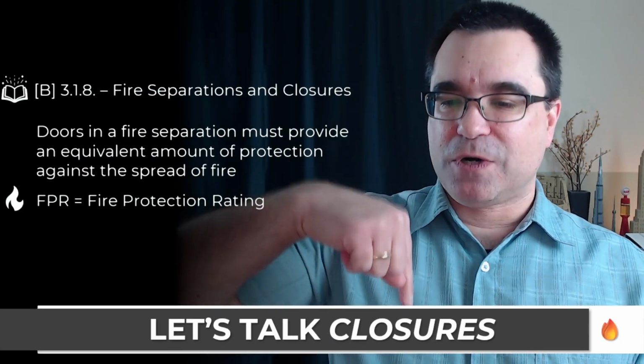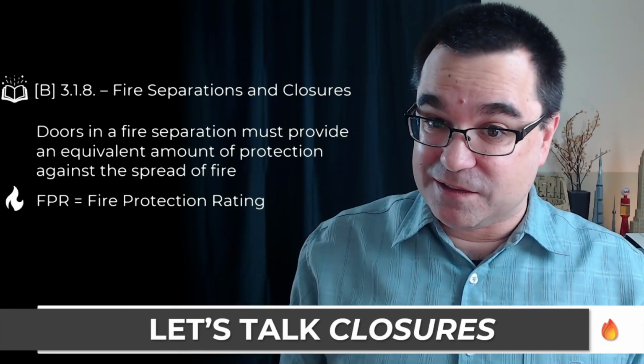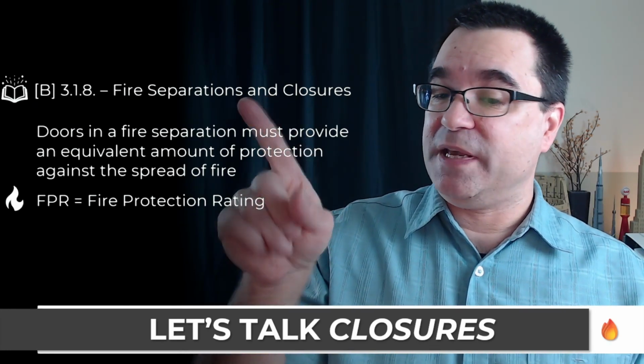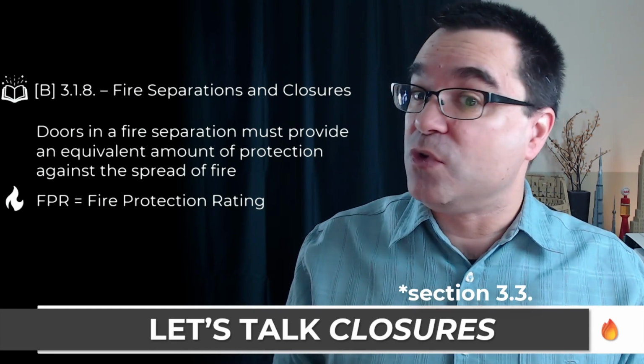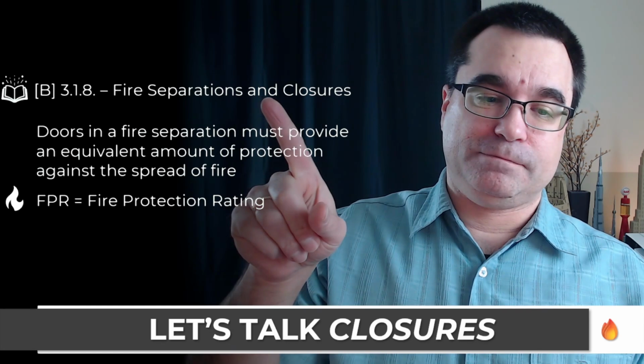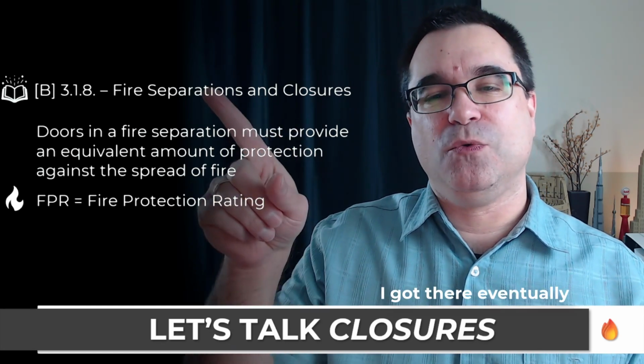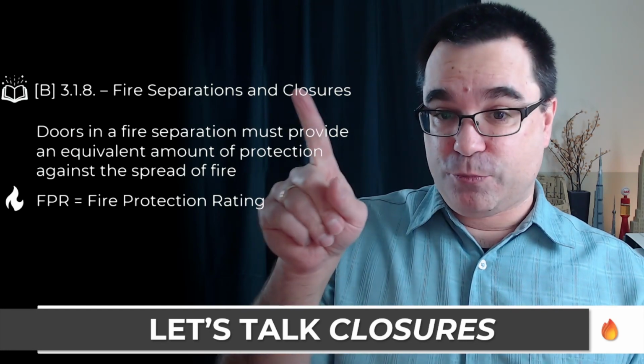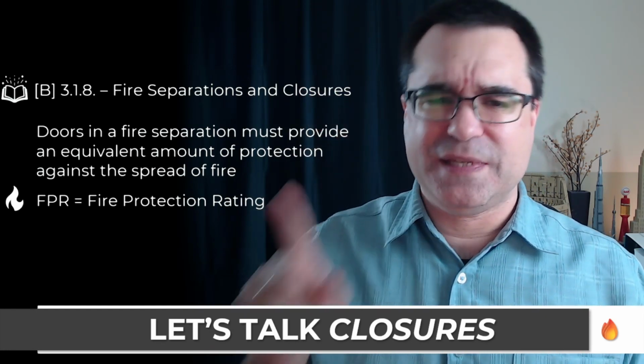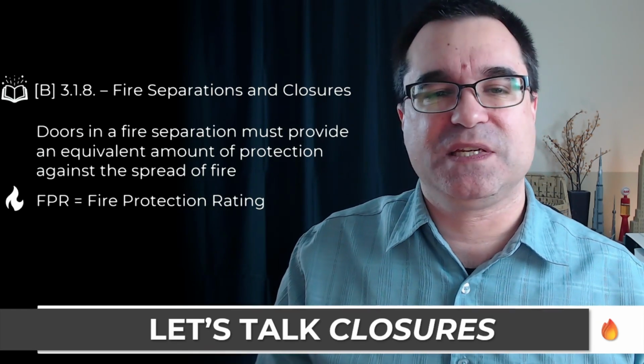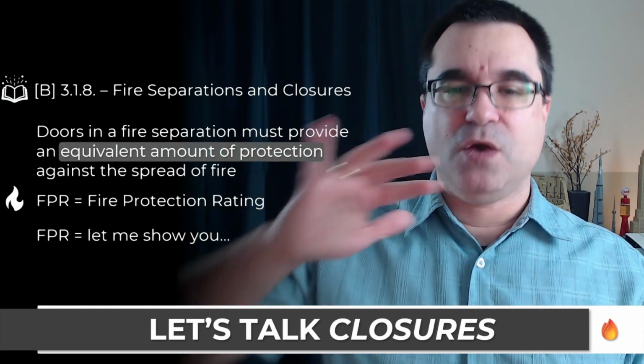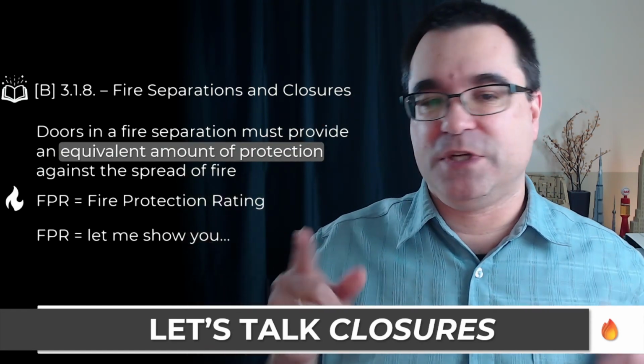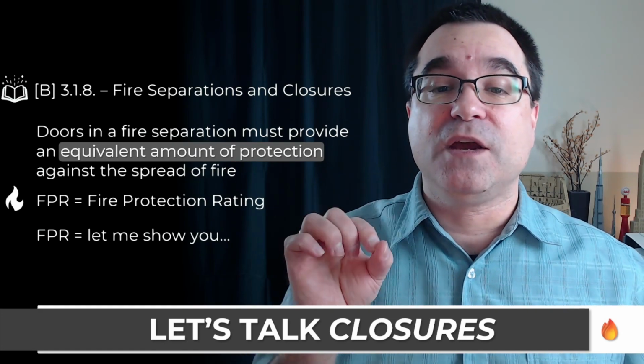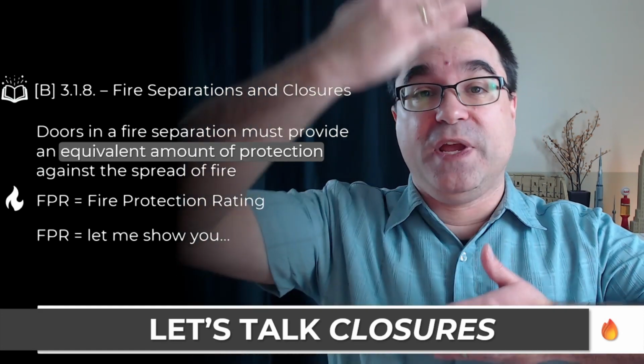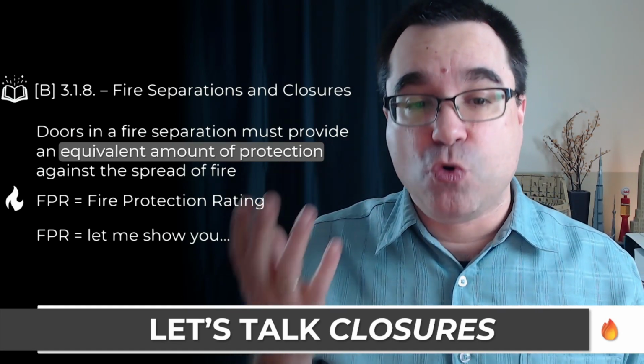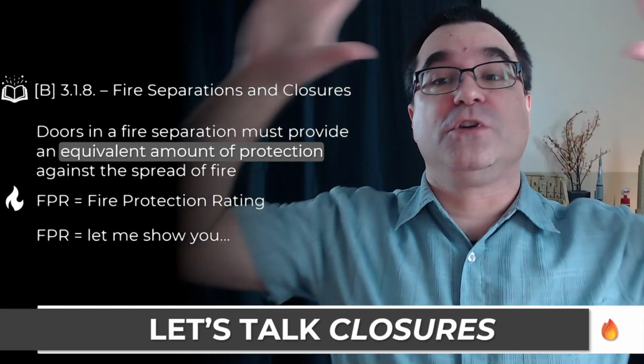So how are closures handled from a fire rating perspective? You have to go to a slightly different place. We're no longer under subsection 3.3. We're actually under subsection 3.1.8, okay? Fire separations and closures. And what this portion of part 3 basically deals with is saying that whatever closure you have in a fire separation, so doors in this case, their contribution to the fire rating of that fire separation must be equivalent to the protection offered by that fire separation.